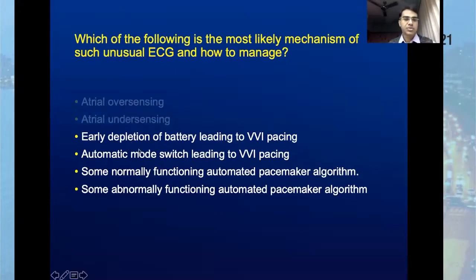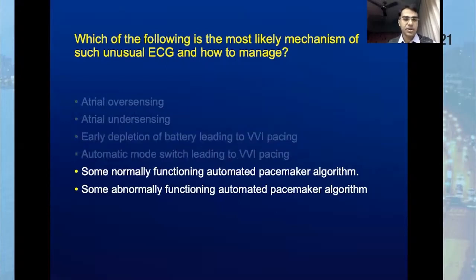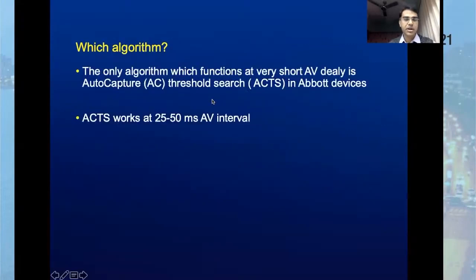So these two possibilities were early depletion or automatic mode switch. The pacemaker can function like V in VVI, but as we know, most likely, although we're not sure without the marker channel, it was almost like A sense V pace happening with a very short AV delay. So we were left with these two possibilities: either some automated pacemaker algorithm is going on, which can be normally functioning, or there can be some abnormality in the automated pacemaker algorithm.